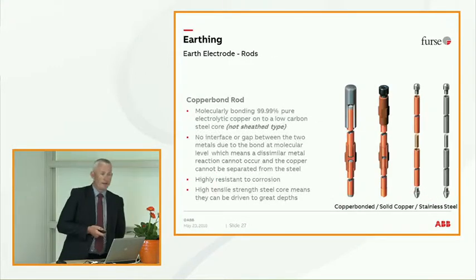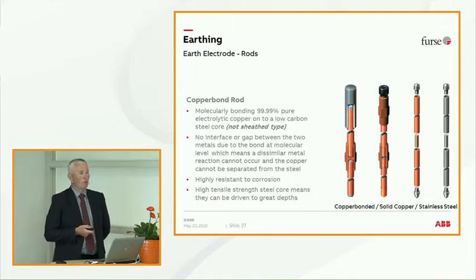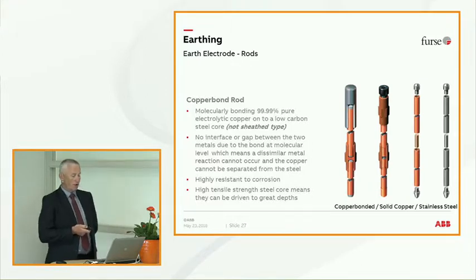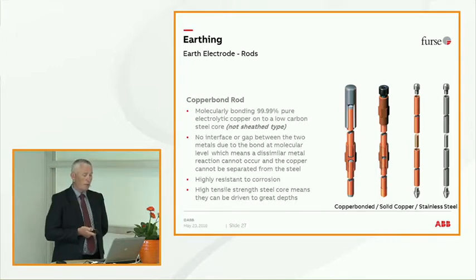When it comes to earth electrodes, these are often used with the conductor, with the ring conductors. The copper bond rods are the rods generally used all over the globe. It's molecular bonded copper, so you've got no issues with galvanic corrosion between the steel and the copper. It's very strong and it's got high resistance to corrosion. High steel tensile strength means that you can drive these to deep depths. So when you get an earthing system, globally it's the copper bond rods normally used.